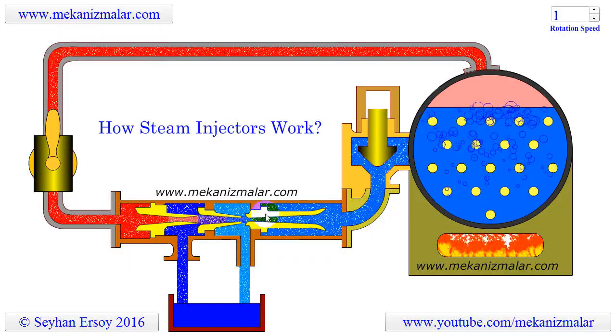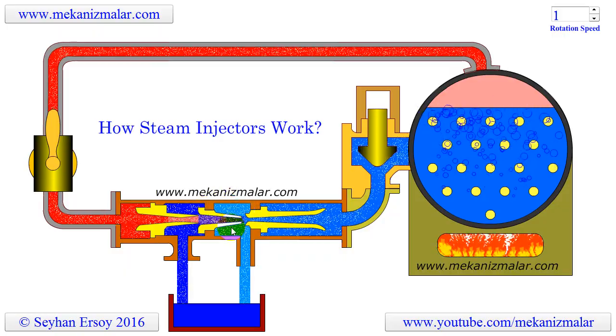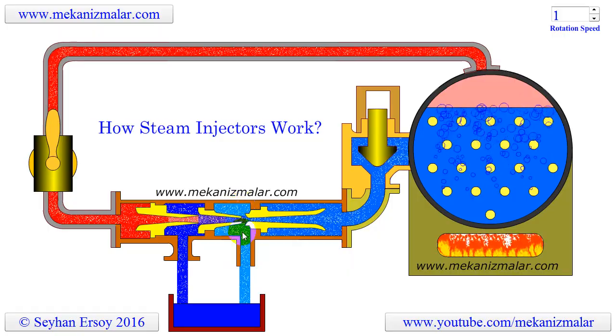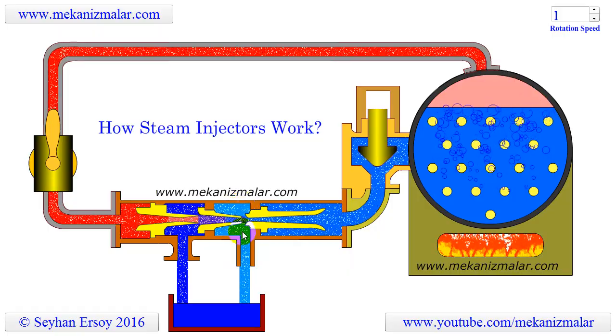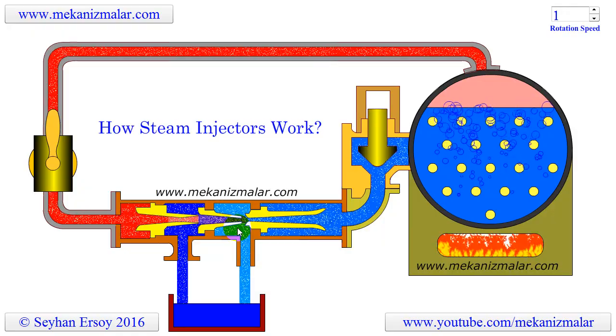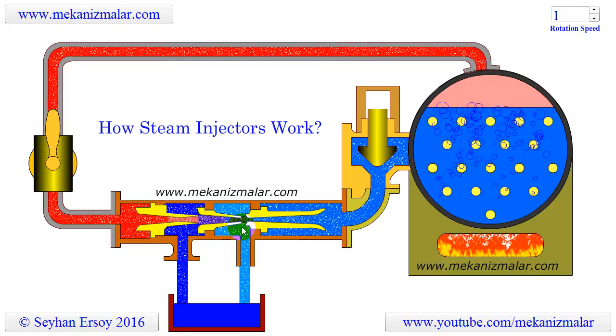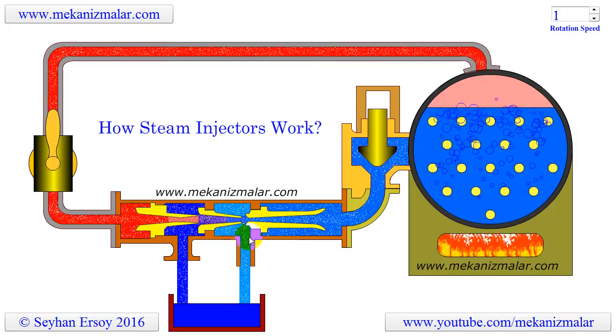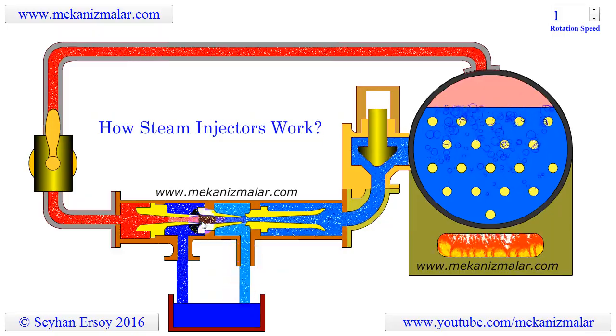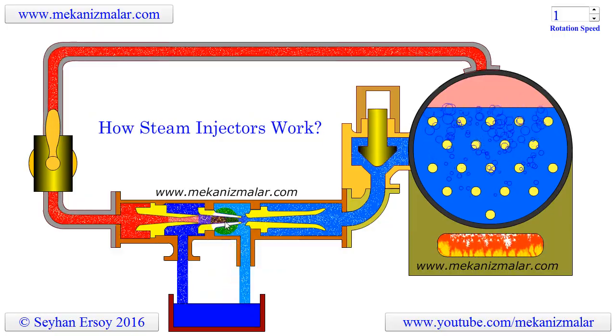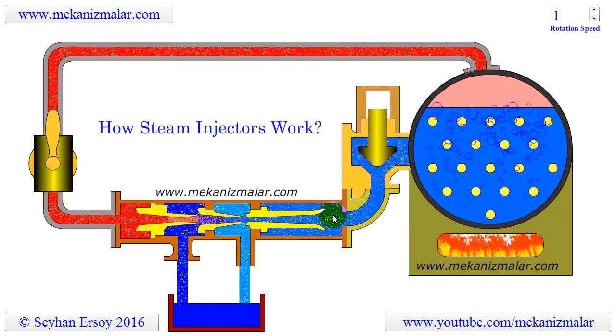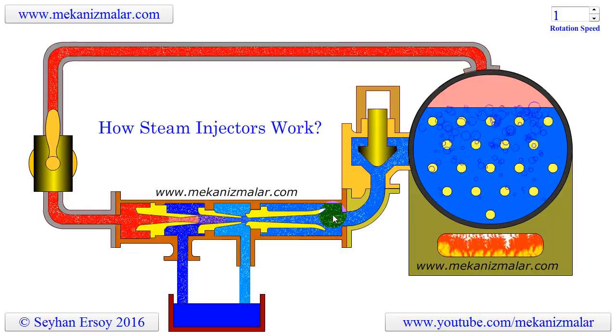What lies between the combining cone and the delivery cone is an overflow chamber. Adding this chamber was the ingenuity of the steam injector's inventor, Henri Giffard. This chamber and overflow pipe allow excess water to be sent back to the reservoir, preventing the steam injector from choking, especially when starting to operate for the first time. It allows the injector to operate smoothly.